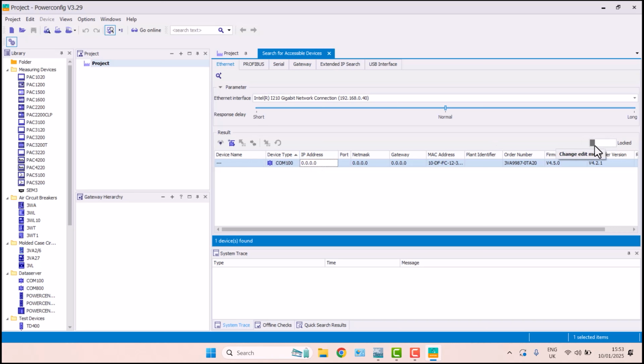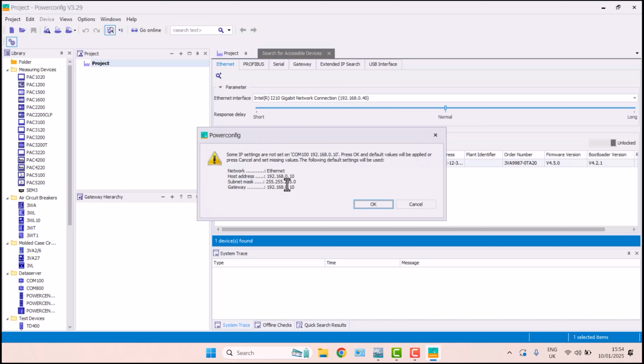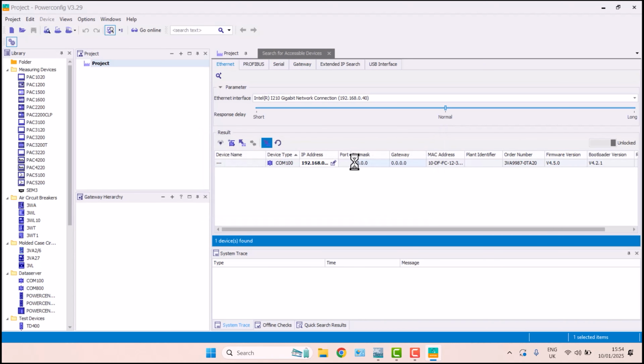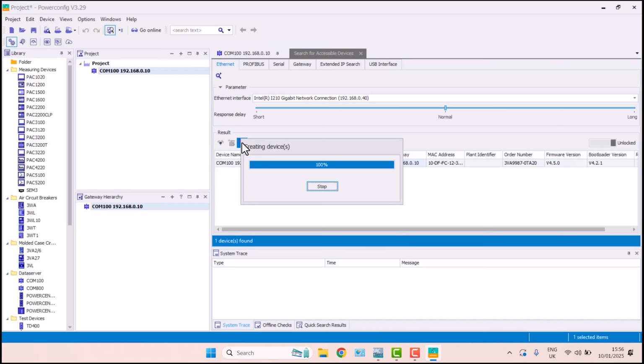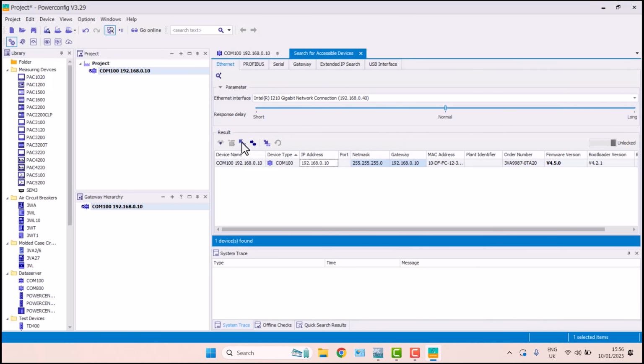So you need to unlock it over here. And then I'm just going to give it the IP address 192.168.0.10. Once I have done that, I need to then download to the device. If I click this, it will then try and get me to automatically update the host address, subnet and gateway. So I'll click OK on that and it'll populate these tabs here and then download to device. So now we've told the COM100 its new IP address and downloaded that successfully. We can then load it to the PC, so that pulls it into this project in Power Config. Once that's successfully done, we can close the accessible device search tab.